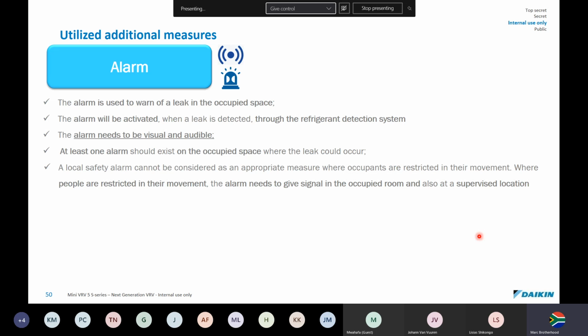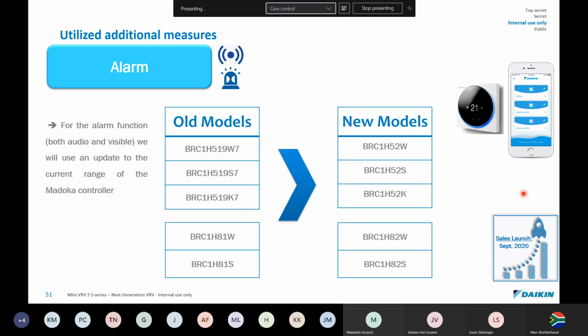It's no good having an alarm in the passage if there's a leak that's been detected. Nobody will know what to do. There'll be panic. What do we do? Is it a fire? Is it this? No, it's just a leak alarm. So each room needs its own leak detection, and it must also be connected to a supervisor who's monitoring the alarm systems.